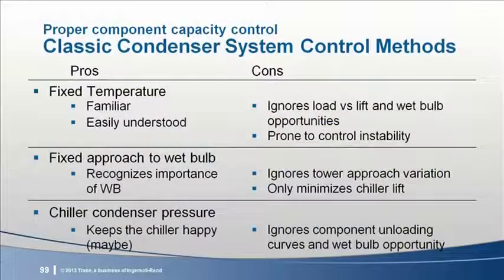As with mixed system analysis, we'll look at condenser system control options as an example again, because it is the most universal application and often the greatest opportunity for savings. Shown here are three often implemented methods of condenser water system capacity control. You can read the short list of pros and cons for each method. In general, all of these control methods share a couple deficiencies.